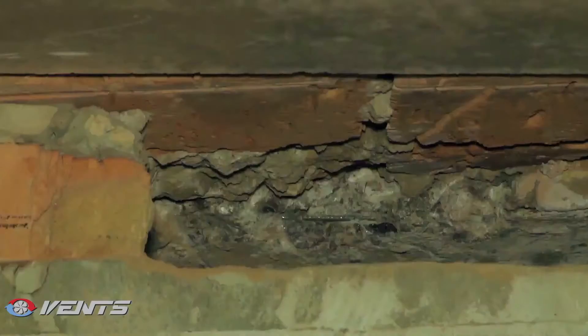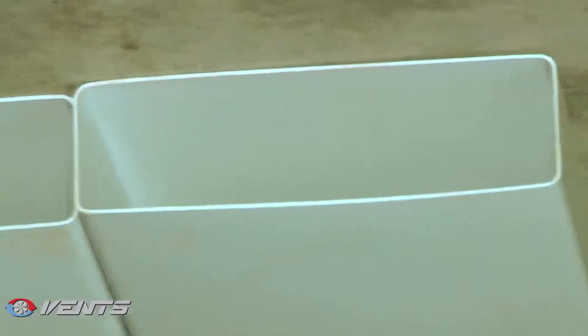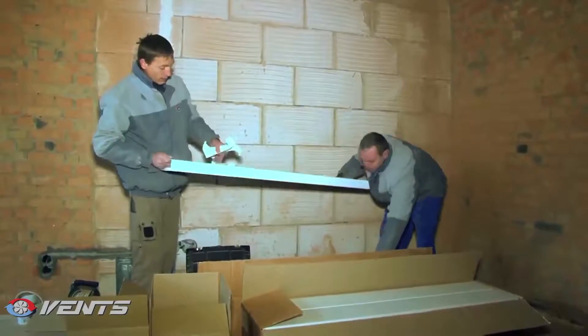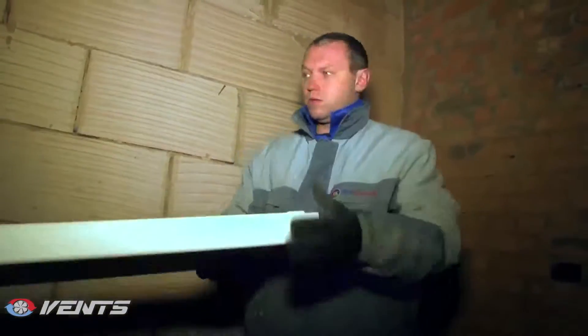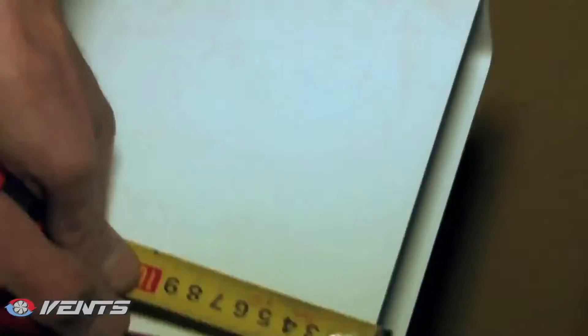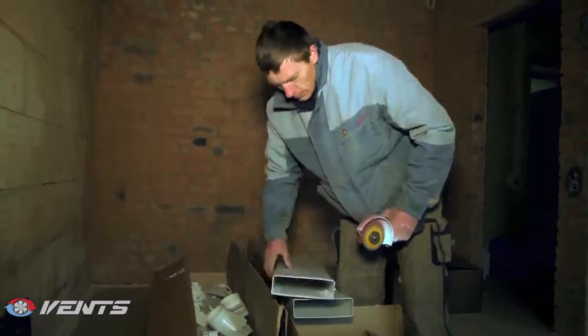The main air ducts reach into the studio kitchen, branching into the bedroom. The rooms have enough space to hide the air ducts behind the false ceiling with gypsum board elements. Considering the moderate air flow rate, the air duct system is made with plastic flat ducting: 60×204 mm for the main duct, and 55×110 mm for the branches.